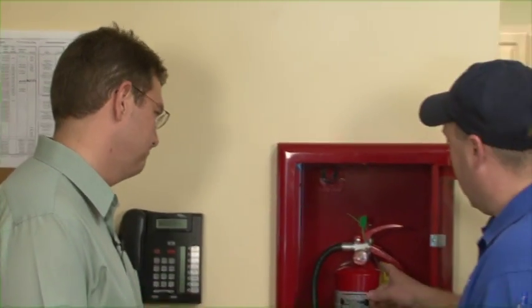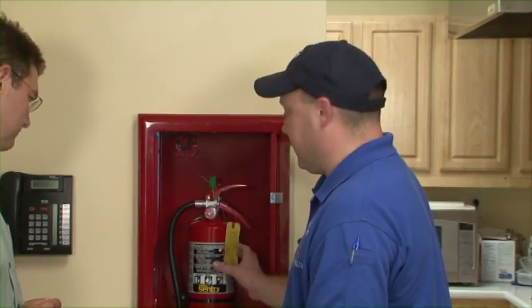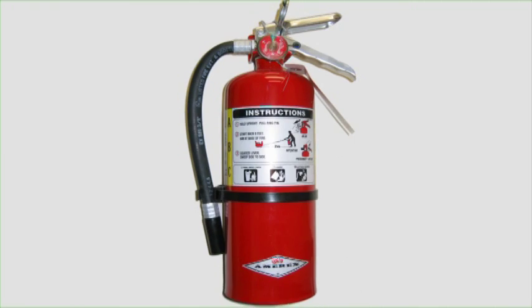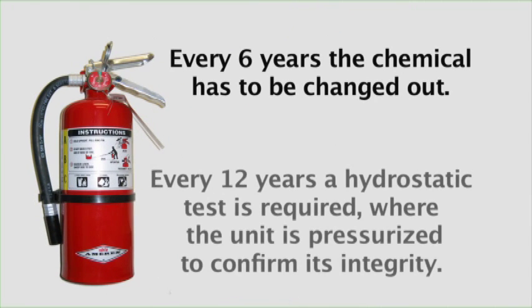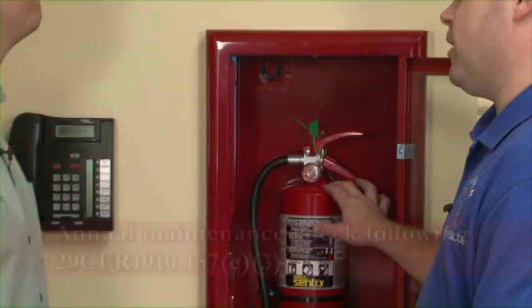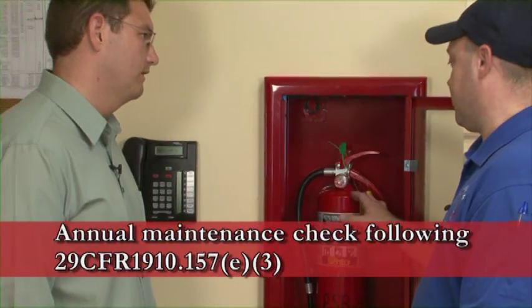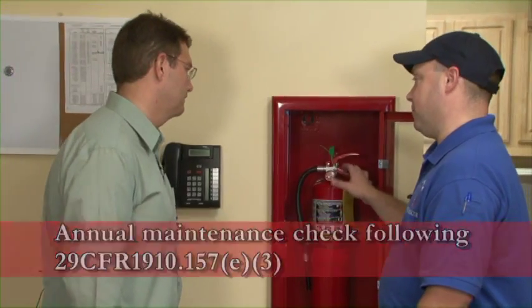Sure thing, Rob. Every 6 years, the chemical that's inside has to come out and be changed out for a fresh chemical. And then every 12 years, a hydrostatic test is required where they take all the chemical out, they take the neck and hose off, and then they pressurize the extinguisher to make sure that there aren't going to be any leaks, so that the pressure required to discharge the chemical in the event that the extinguisher has to be used is going to be able to be maintained.